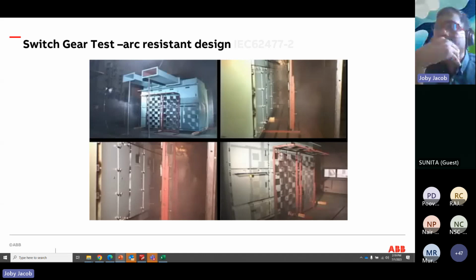It can certainly hit you, or if you are standing in front of a breaker or a panel, where you stand, on the hinge side or on the door side, matters. If an arc flash happens and you are at the door side, then the door can open and the flash can hit you if it doesn't have a proper kind of explosion vent. I don't know whether you are using ABB medium voltage breakers, UniGear breakers, you can see the trapezoidal shape at the top.